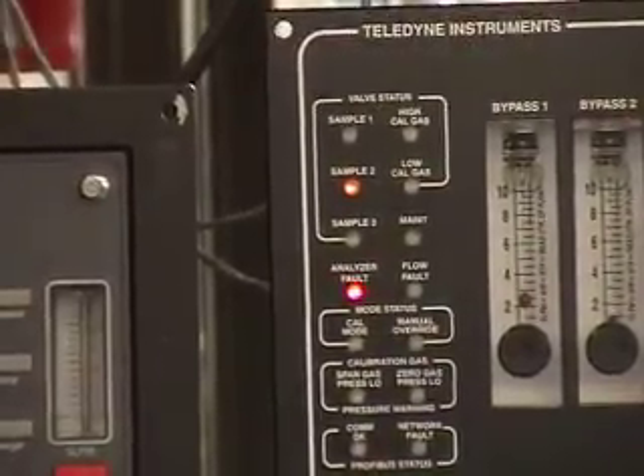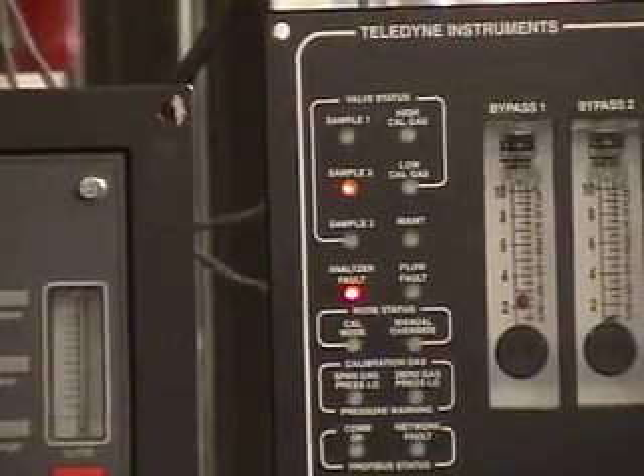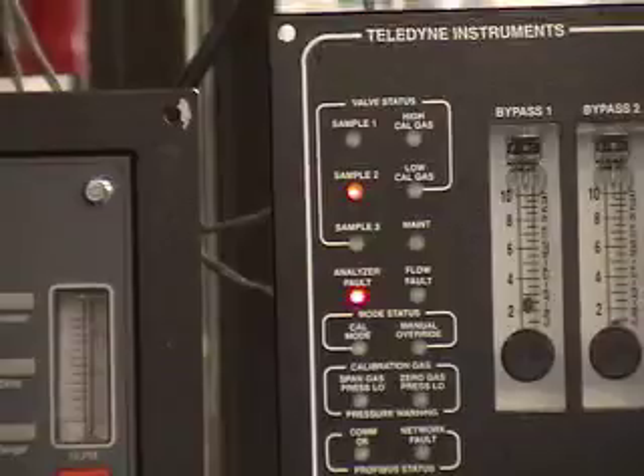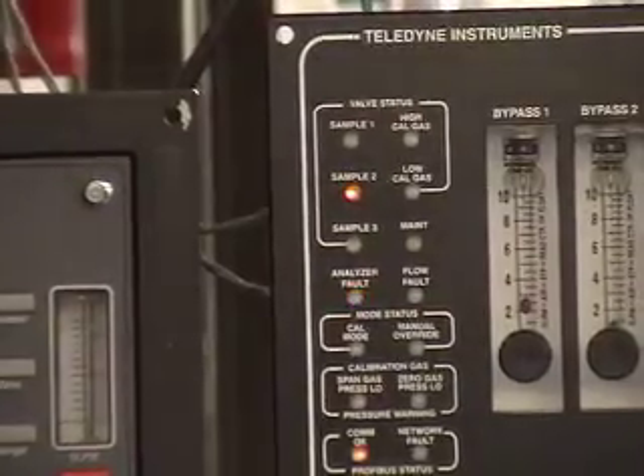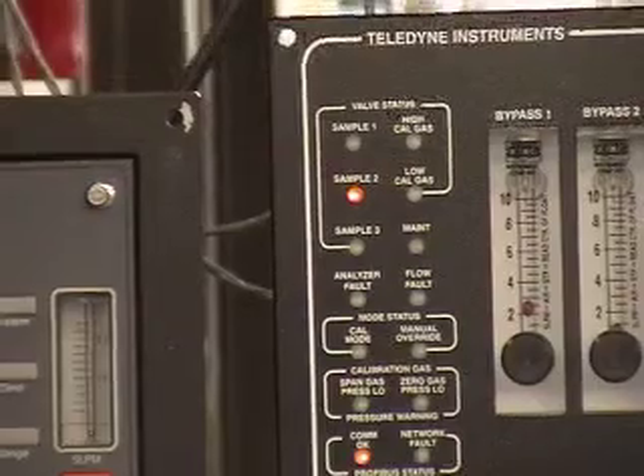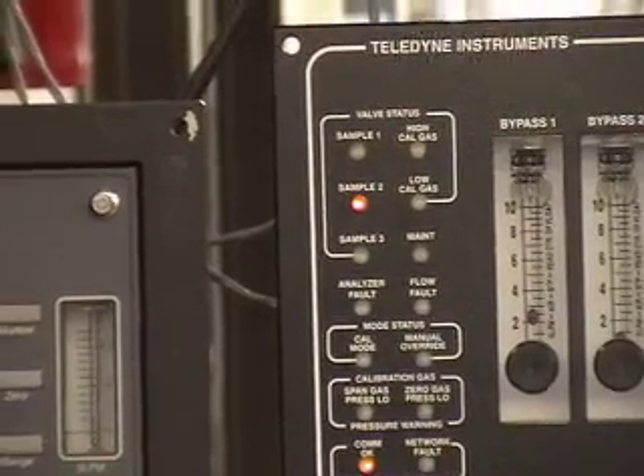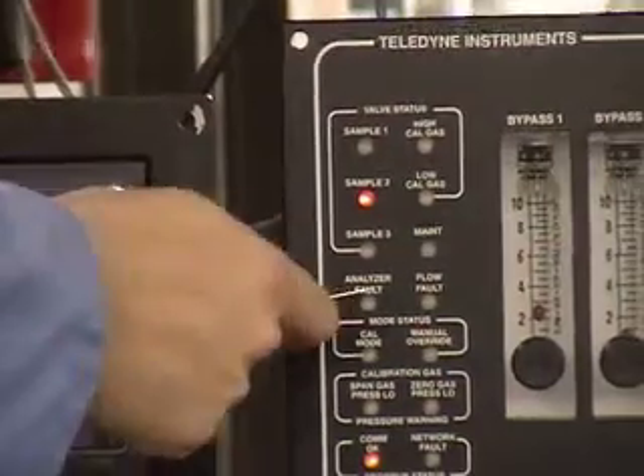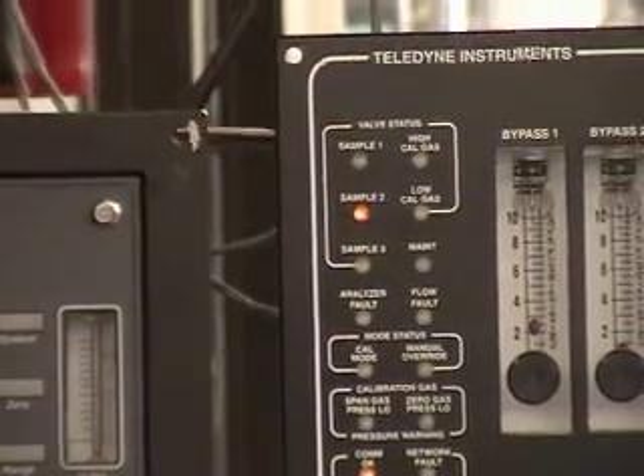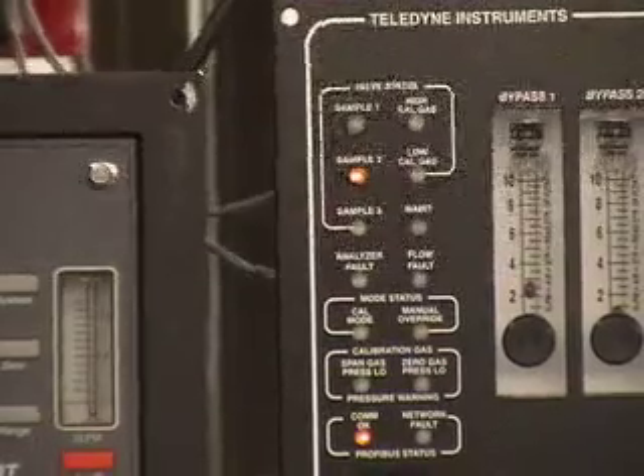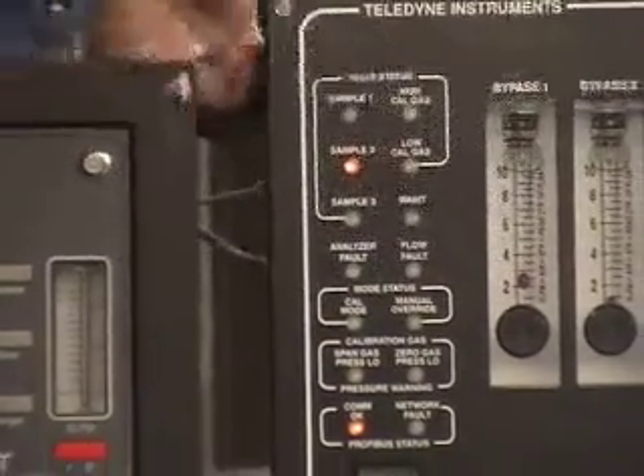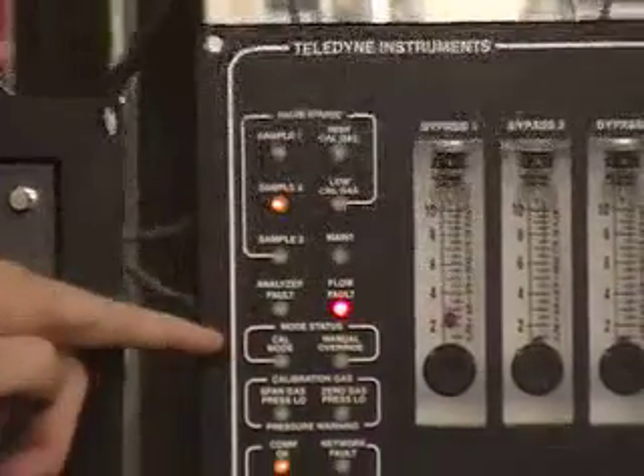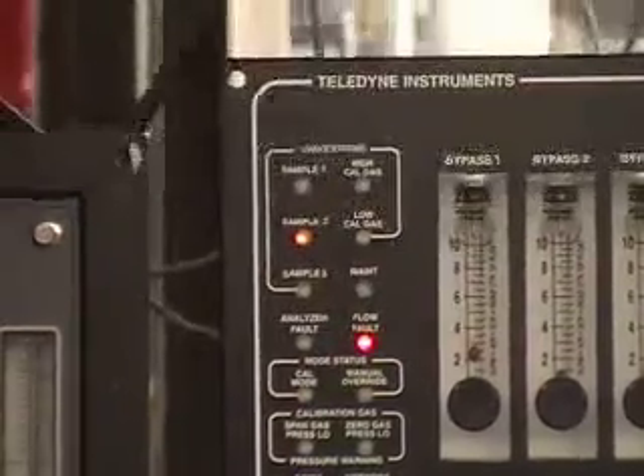I'm going to connect it back in. And connect the RS-232 back. Communication is established again, and the analyzer fault went away. And now you will see there is a flow fault light, because there is a flow switch. Like I said in the beginning, there is a flow switch. And to mess with the flow switch, I'm going to disconnect the flow switch so that it's open and the flow fault comes in. Like there is no flow right now.